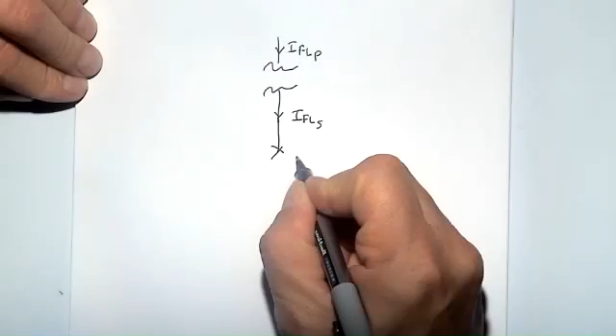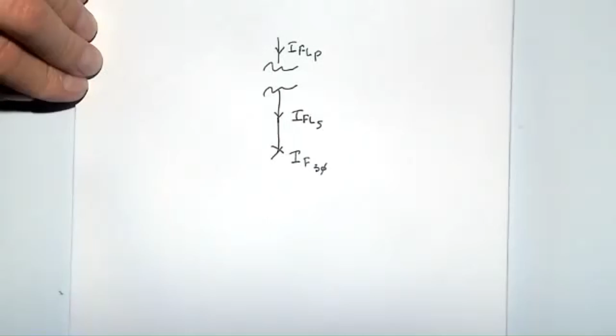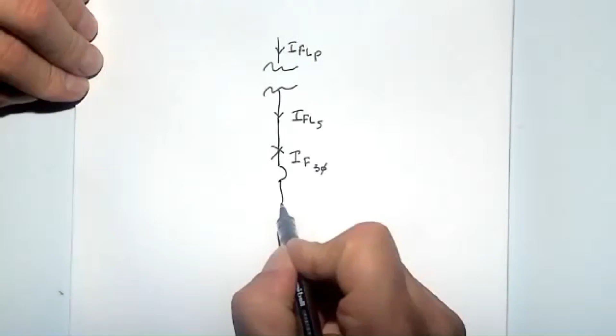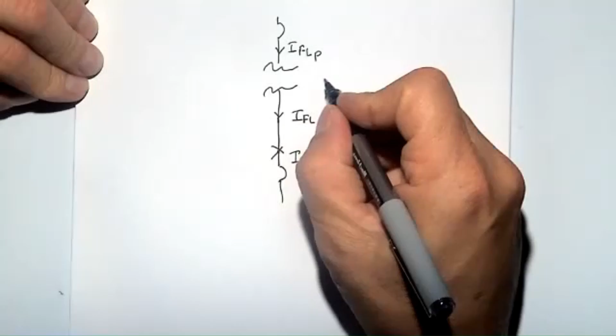Okay, so let's get into the fun stuff. Let's calculate the full load amps on the primary and secondary of a transformer. Here, I full load on the primary, I full load on the secondary, three-phase fault current, I fault three-phase here, and that's going to help us determine the wire sizes on the primary and secondary, as well as perhaps the breaker sizes here on the secondary and there on the primary. Now we're going to use the information from the transformer. So again, we're gathering information from the transformer's nameplate.